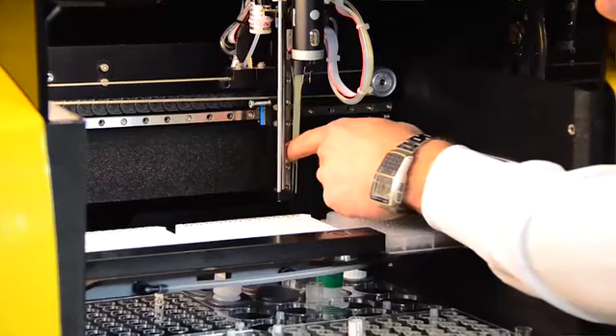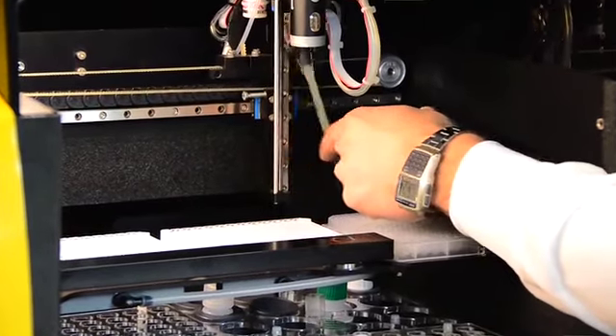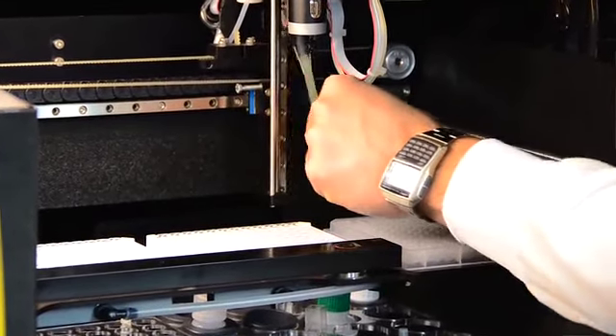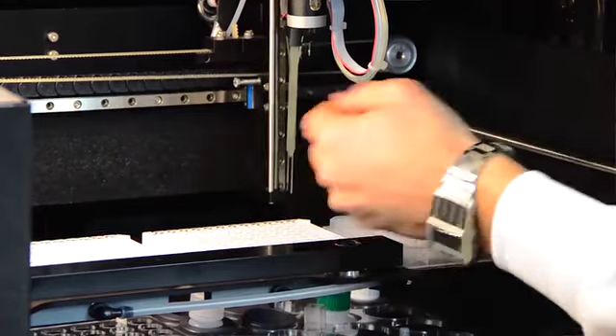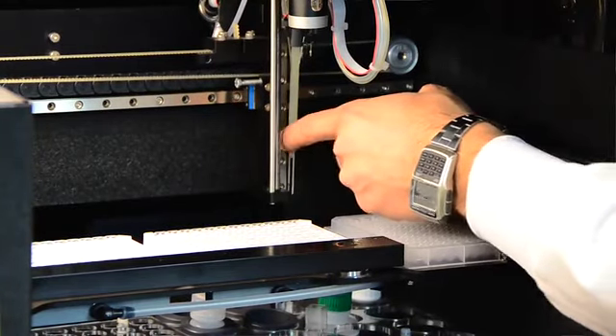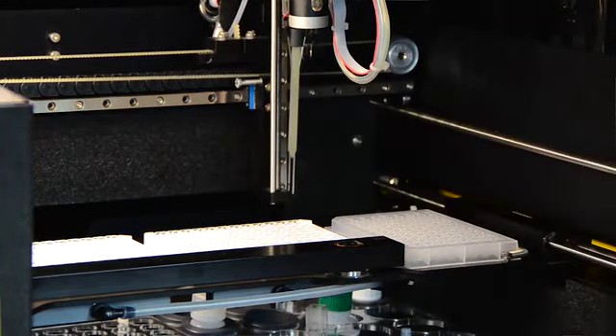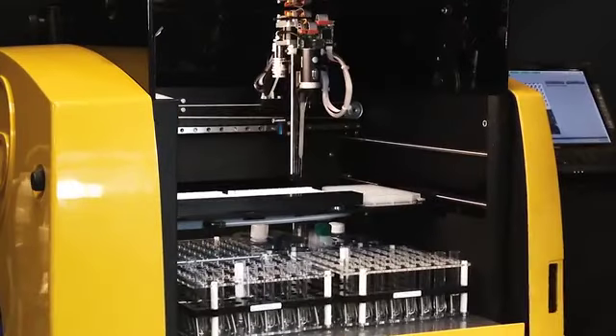The other great feature is that it's a snap-back probe. It's held on by a magnet, and so if something hits it on the horizontal plane, it will snap back into place. Now, the way that the probe detects liquid is through a conductance system. So like I said, it's a single probe dual needle. Both of those needles serve as the conductance probes. So when they are in liquid, it closes the circuit and tells the probe that you are in fluid.